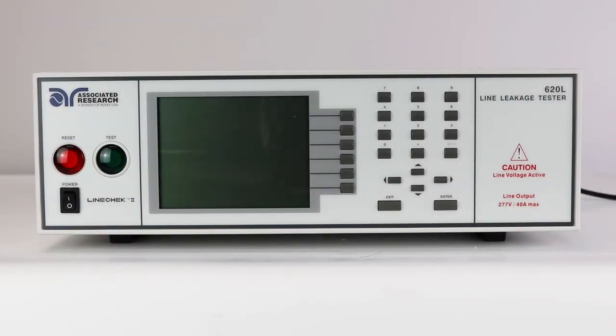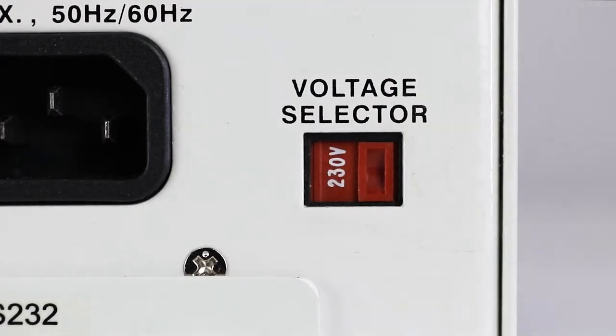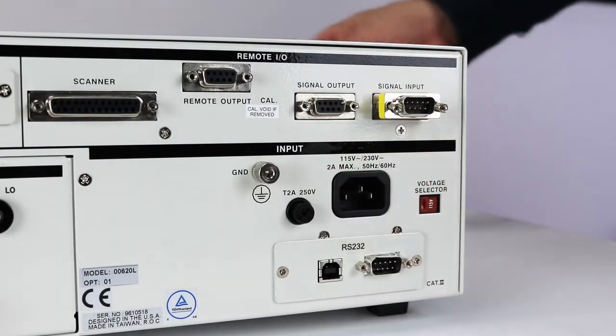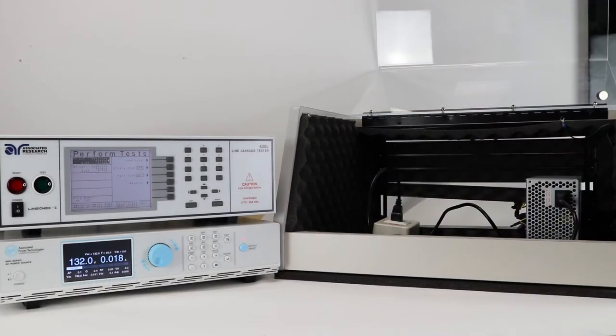First, you'll need to power up the LineChek instrument. Check to be sure the correct input line voltage has been selected on the rear panel, either 115 volts AC or 230 volts AC. You'll also need to insert the remote interlock key into the signal input terminal on the rear panel. The instrument will not output voltage unless you use this key. This allows the user to wire the instrument to the doors of the DUT enclosure. This is a safe workstation best practice.